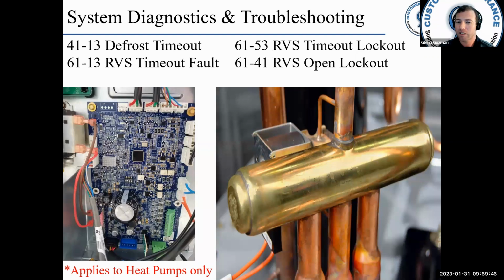4113 defrost timeout, 6153 reversing valve timeout lockout, 6113 reversing valve timeout fault, and 6141 reversing valve open lockout. This applies to heat pumps only. The 4113 is a defrost timeout. After a predetermined length of time at a possible coil frosting condition, which must be below 35 degrees, defrost will be initiated. Coil temperature is monitored and will complete the defrost cycle once it reaches a target value dependent on the model and the outdoor air temperature value.